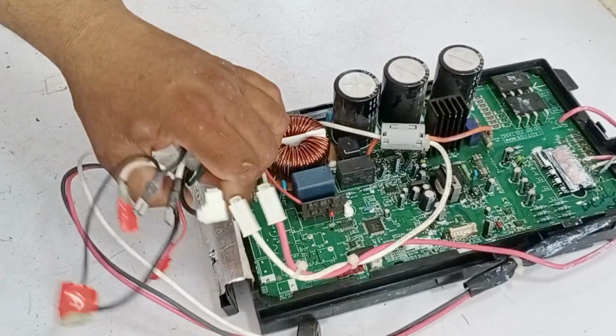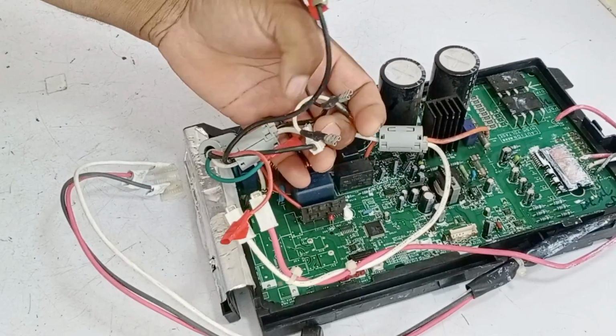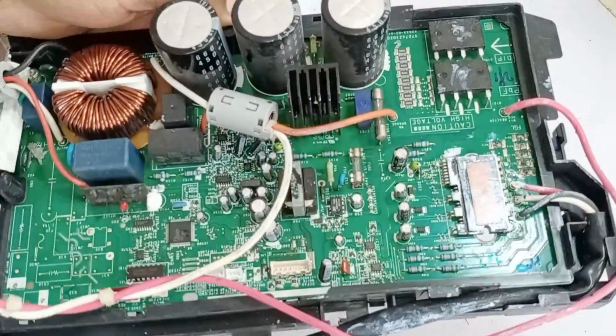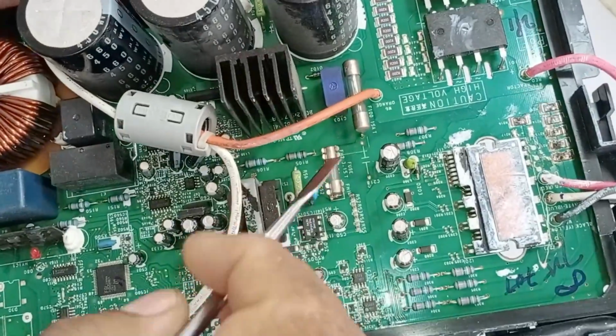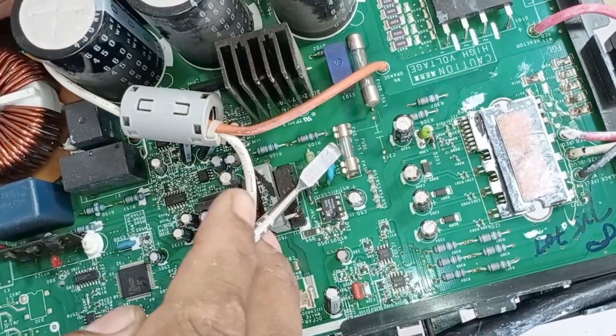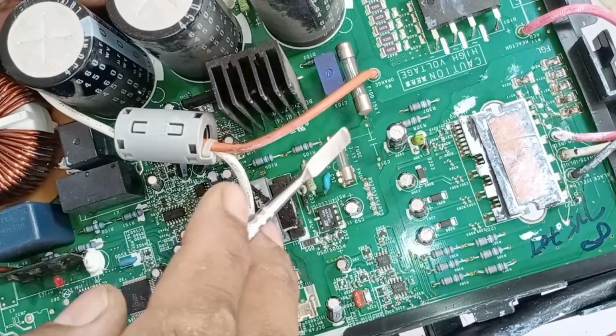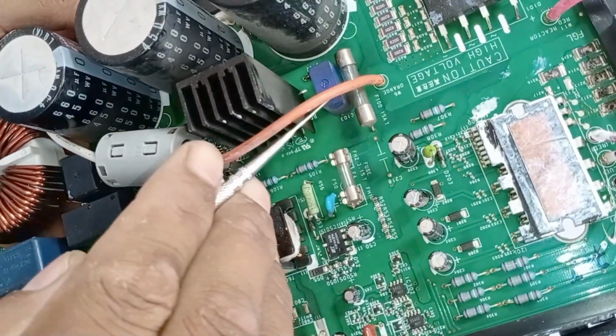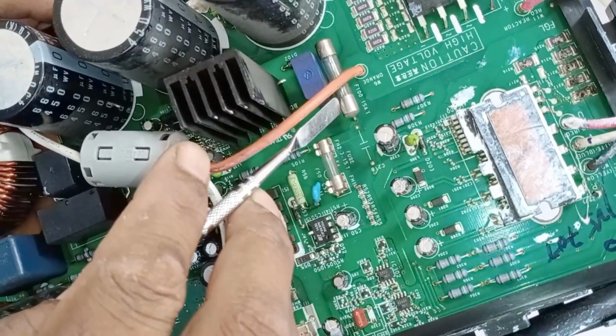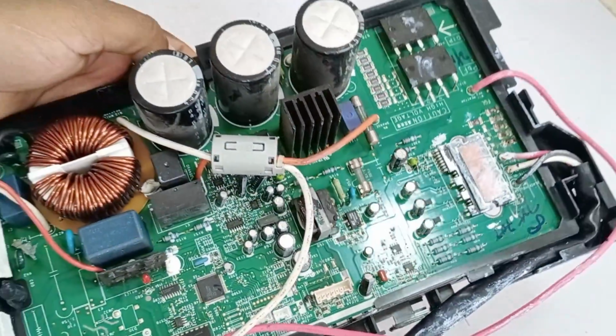The customer has removed all the fuses that were attached to these spade connectors, but 2 fuses are installed inside the circuit board. Both these fuses are fine. This one is 3.1 amps, and this bigger fuse is 15 amperes. This fuse is also fine, but it still failed the physical test.